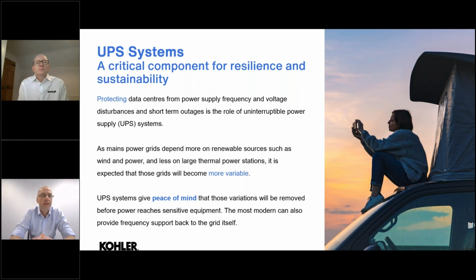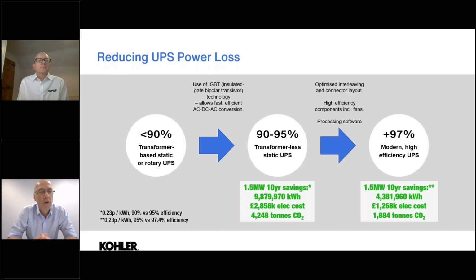Thanks, Ian. So yeah, the UPS system, obviously a very critical component for the data center for resilience and sustainability. The UPS's main role is to smooth out the supply frequency and voltage disturbances over a very short time. And we see as main power grids depend more on renewable sources such as wind and solar power and less on the thermal power stations, it's expected that these grids will become more variable. So having that UPS in the system gives us the peace of mind that those variations will be removed before reaching sensitive equipment. Okay, and also, as Ian mentioned, the most modern UPSs can also provide a frequency support back to the grid itself.